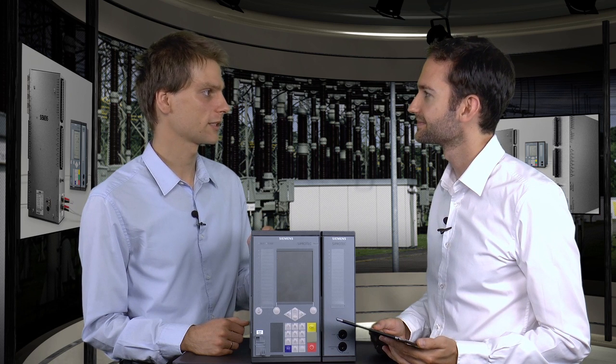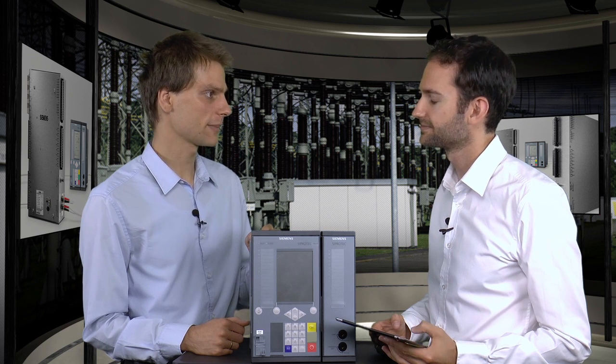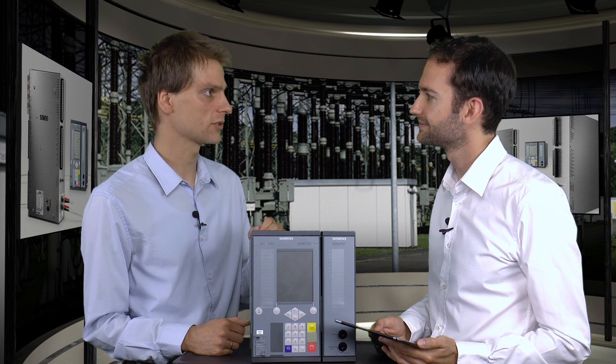SIPROTEC devices are a special part of a high-voltage substation, and with process bus, the architecture of high-voltage substations will change dramatically. With process bus, the measurement of voltages and currents, which is needed for a protection function, is no longer transmitted via thick copper cables. Today we use thick copper cables for connecting the sensors to the protection relays to be EMC resistant.